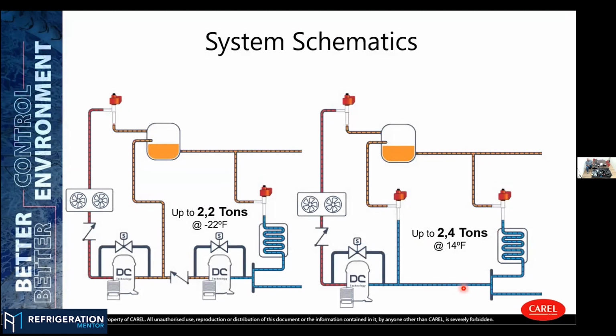Basically, for medium temp applications, we can manage both high pressure valves, bypass valves, and also the compressor for medium temp directly. And in case of low temp applications, we can manage the high pressure valve, the low temp compressor, and also a parallel compressor, just to make sure that we can reach higher capacities and maximize the energy efficiency. If we do this in a single stage operation, the COP would be very, very low. So we can increase this by having two compressors connected in a booster mode.